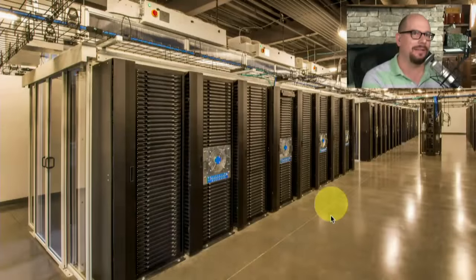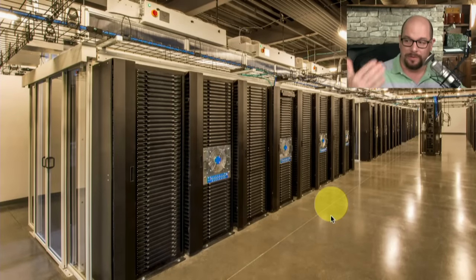A lot of the equipment I used to work with, before there was such emphasis on hot and cold aisles, had fans on the side that would pull air from side to side. People said, no, we don't want side to side, we need air to go front to back because we've set up all these hot aisles and cold aisles. It needs to flow properly so we have the most efficient setup.